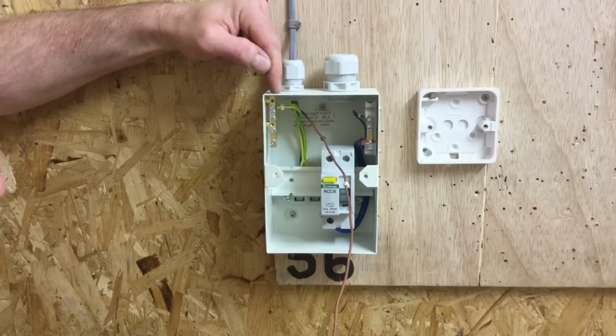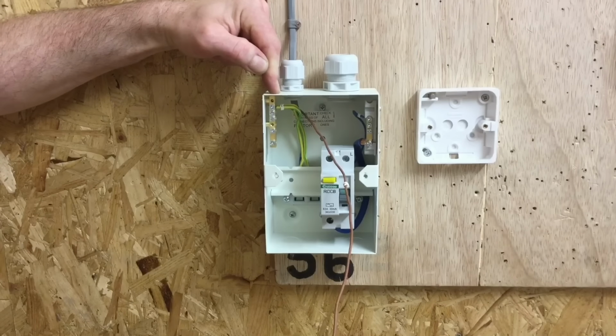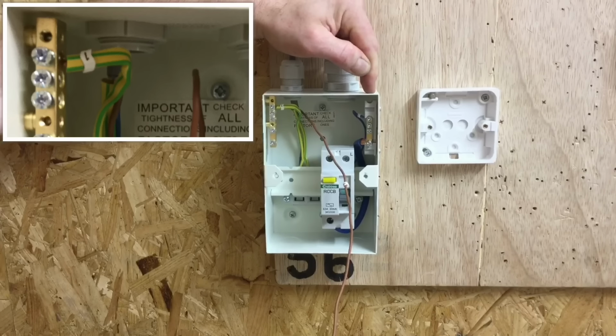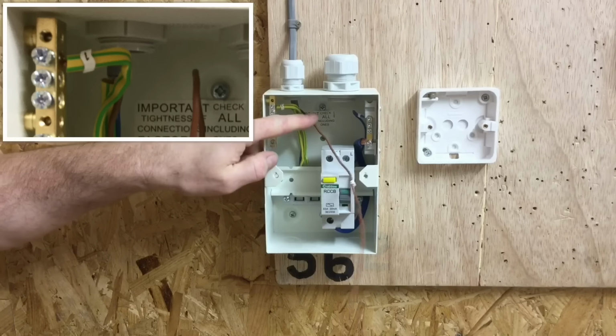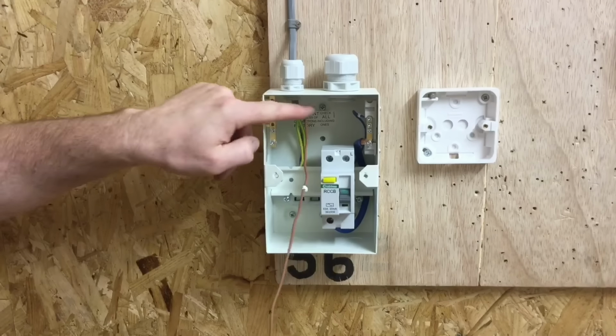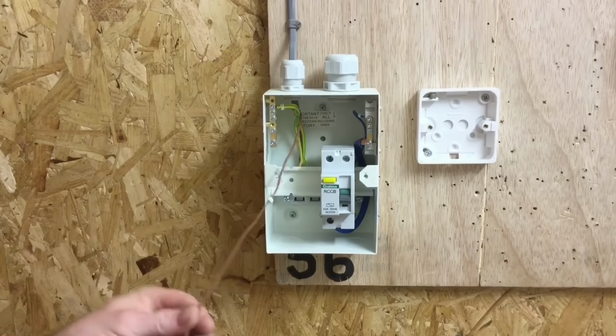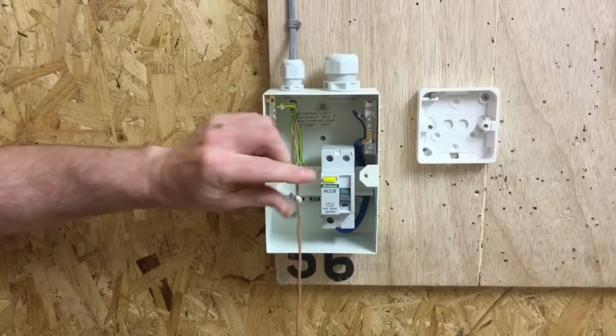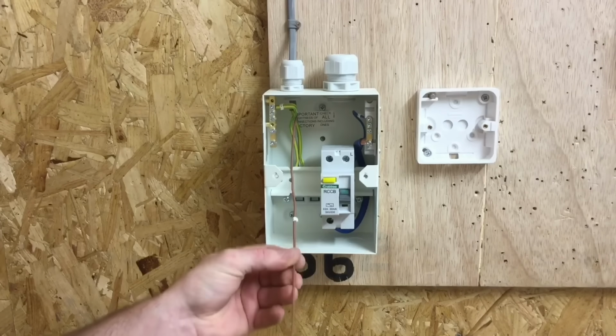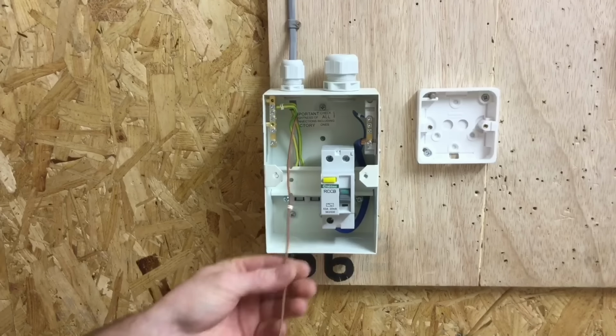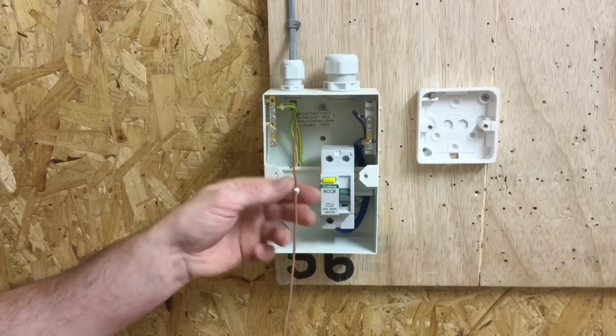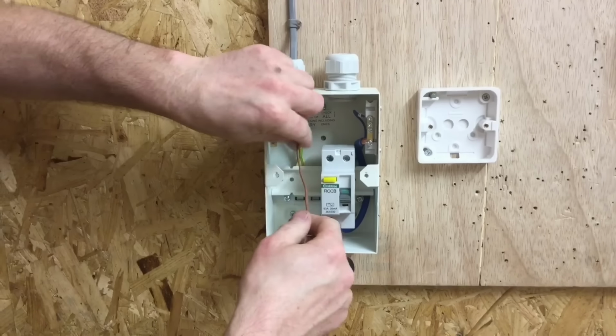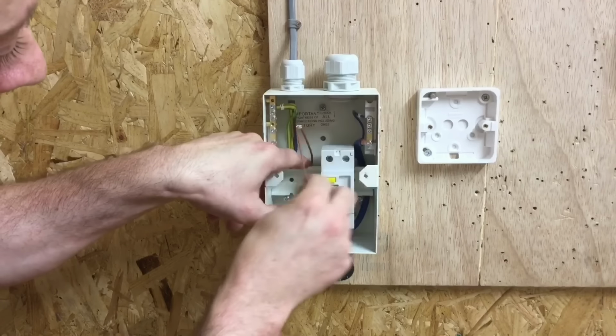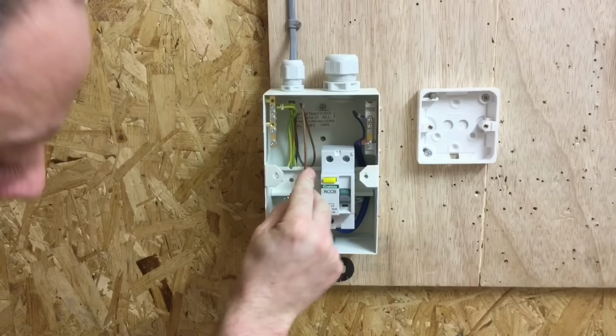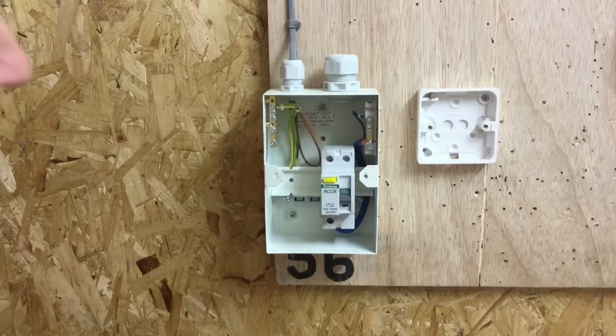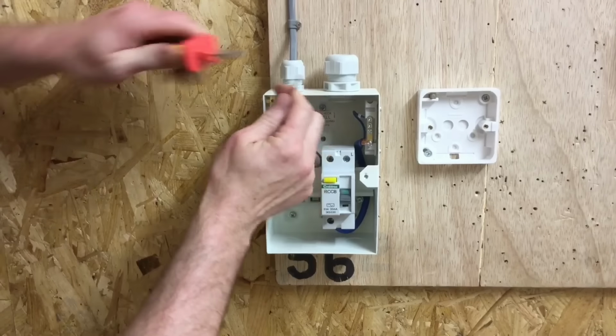So I've terminated my circuit protective conductor into the top of the earth bar. I've connected my neutral into the top of the neutral bar, and now it's all about dressing the line conductor, which is also identified with the number one, so it can pop around and into the top of the circuit breaker. I've shown you in a previous presentation how to fit Crabtree Starbreaker circuit breakers. It's for a lighting circuit, so it's rated at 6 amps. We're simulating a domestic dwelling, so it's a type B circuit breaker. So I'm going to come down the back, curl it over and into the top like so. I need to cut it back, and I need to double it over.